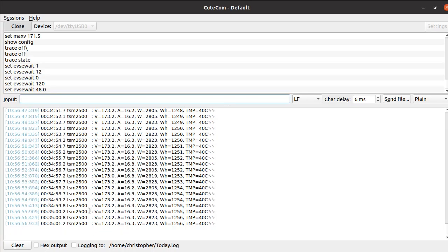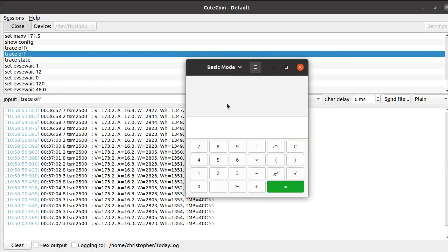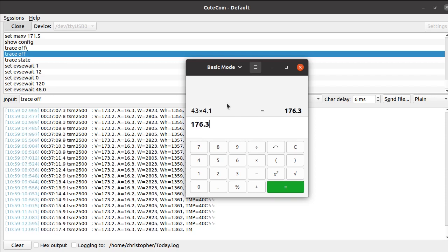Okay, so I want it to stop and settle with the cell voltages at 4.1 volts. There's 43 cells, and I want a finish voltage of 4.1 volts per cell, so my finish total voltage needs to be 176.3. That's what I want to set the charger to. I probably want to set it a little higher than that so it settles back to 4.1 volts per cell once it's sitting for a bit.